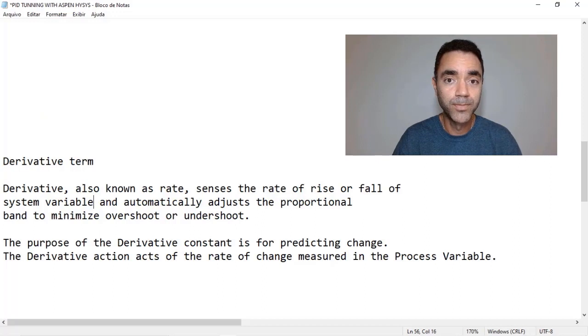And the main purpose of the derivative term is to predict what can happen in your variable. So it's most useful when you have a dead lag, that is when you do a change and you have a long time to have a response in your system.